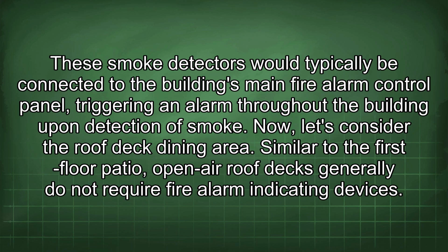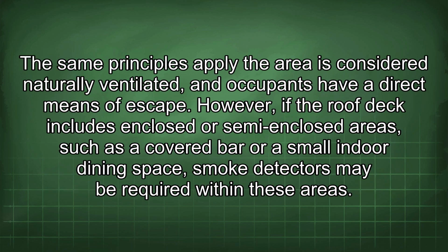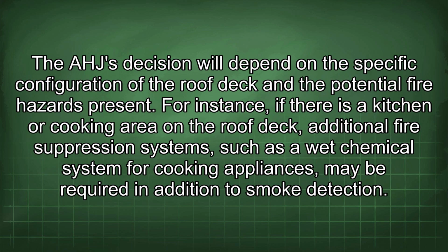Similar to the first floor patio, open-air roof decks generally do not require fire alarm indicating devices. The same principles apply. The area is considered naturally ventilated, and occupants have a direct means of escape. However, if the roof deck includes enclosed or semi-enclosed areas, such as a covered bar or a small indoor dining space, smoke detectors may be required within these areas. The AHJ decision will depend on the specific configuration of the roof deck and the potential fire hazards present. For instance, if there is a kitchen or cooking area on the roof deck, additional fire suppression systems, such as a wet chemical system for cooking appliances, may be required in addition to smoke detection.